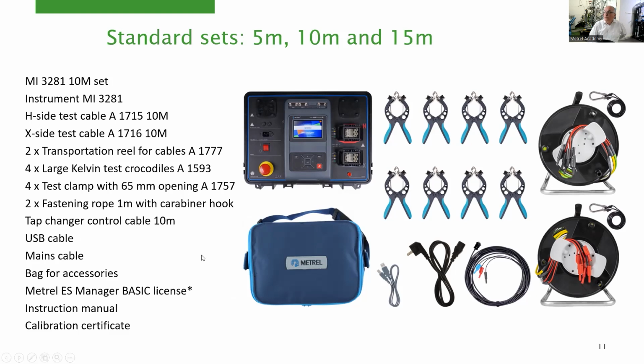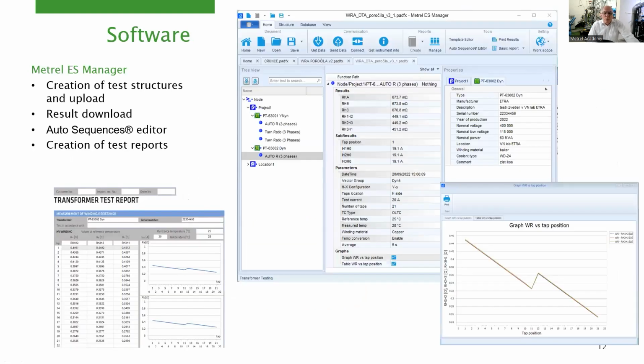That covers the accessories altogether. For sure, this instrument can be controlled locally on the instrument itself, but usually, as with Metrel, we always have supported PC software, which enables you to prepare the test in advance and upload it to the instrument. Results saved on the instrument can then be downloaded back to the PC software, where you can analyze the results, create test reports like this, analyze the results in numerical and graphical form, and for sure you can also prepare the auto sequences here if you are an advanced user.